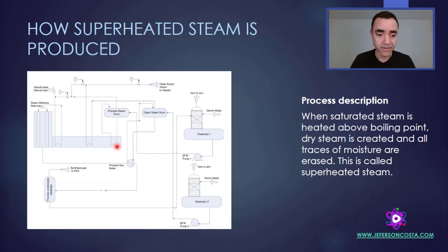I have a thermosiphon that is connected with the flue gas that is produced during the steam methane reforming, because I burn gas to increase the temperature of the system, and this burning leads to a high temperature. I am able to use this temperature of the flue gas to heat up my water and with this produce steam. So I have water going down here, heating up, and it returns as saturated steam, because it is in equilibrium with the water that is inside the steam drum.